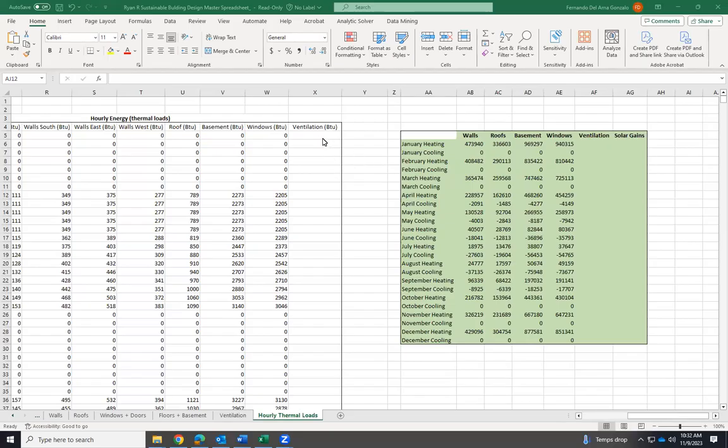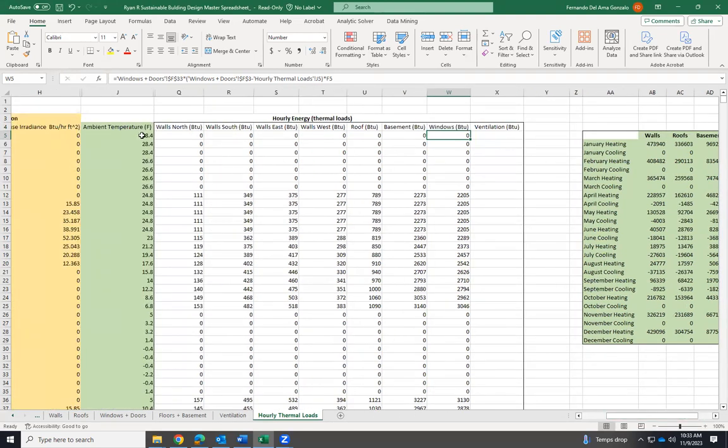Hello everyone, in this video I'm going to explain how to calculate the ventilation hourly loads, and then the monthly loads for ventilation and the solar heat gains. For the rest of the formulas, we know that we have the UA value, the thermal transmittance times the area of windows, roofs, walls, whatever, times indoor temperature minus the outdoor temperature. And the thing is now the outdoor temperature is changing hourly.